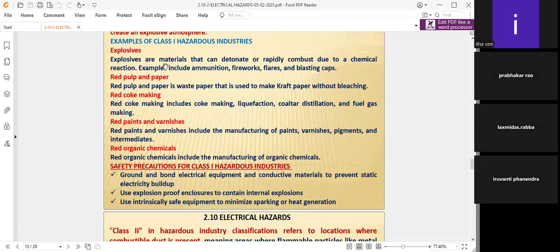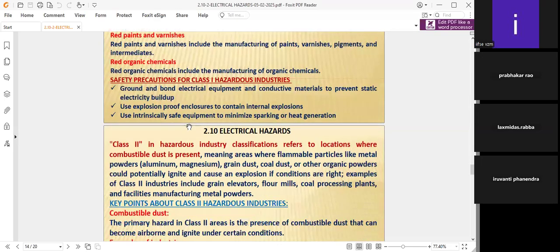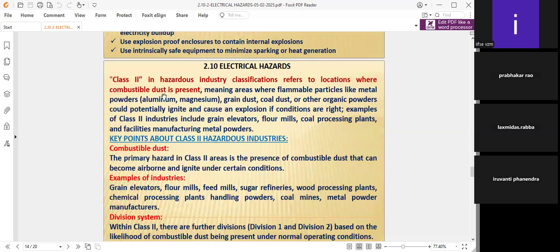This is very important: class 1 hazardous areas of industries. Now coming to class 2 hazardous areas. Class 2 refers to locations where combustible dust is present. As another gentleman is telling, it is combustible dust, not simple dust. Combustible dust means that with atmospheric oxygen the dust will burn immediately. It catches fire also.